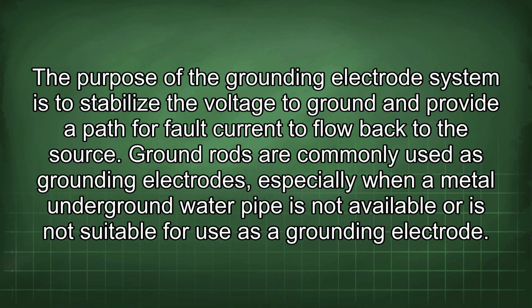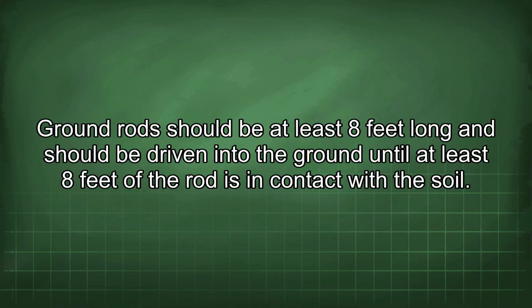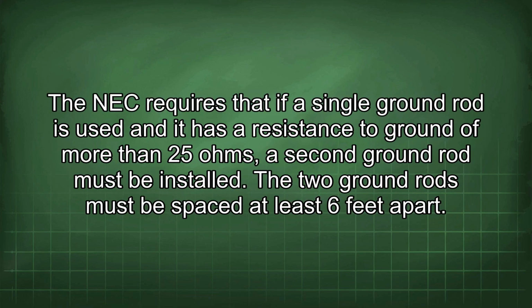Ground rods are commonly used as grounding electrodes, especially when a metal underground water pipe is not available or is not suitable for use as a grounding electrode. A ground rod should be at least 8 feet long and should be driven into the ground until at least 8 feet of the rod is in contact with the soil. The NEC requires that if a single ground rod is used and it has a resistance to ground of more than 25 ohms, a second ground rod must be installed. The 2 ground rods must be spaced at least 6 feet apart.